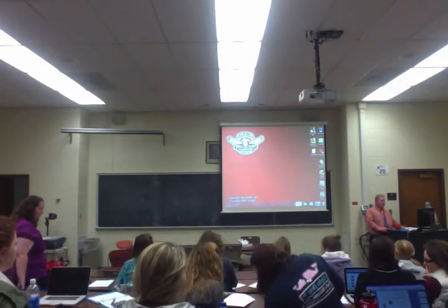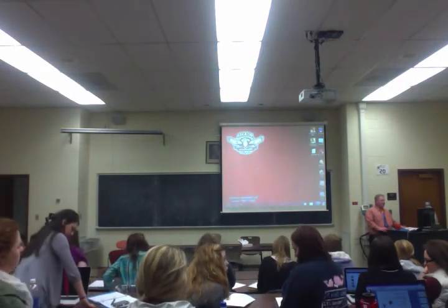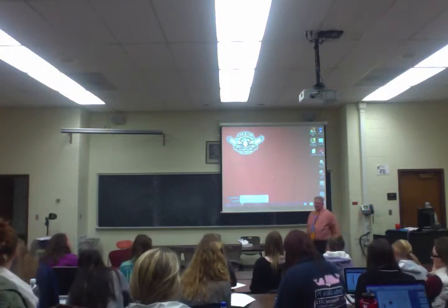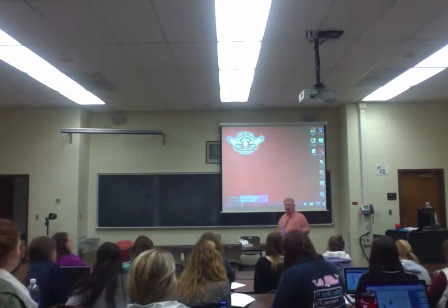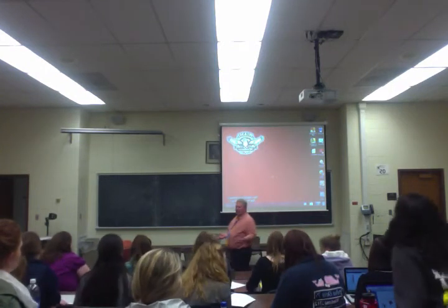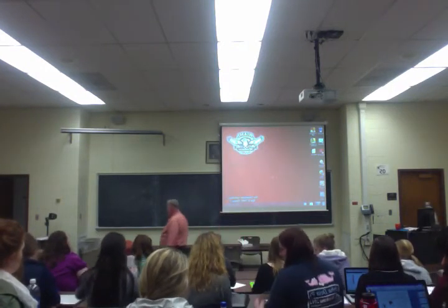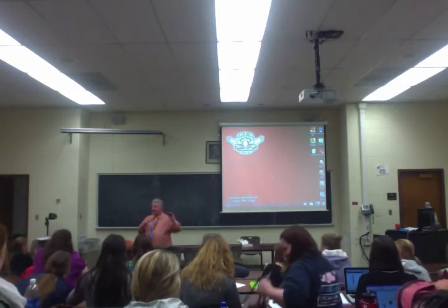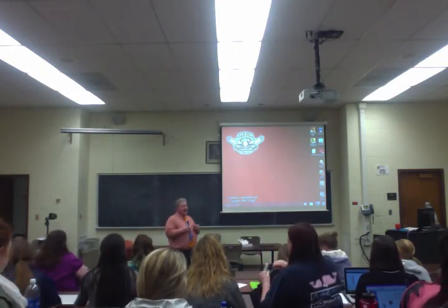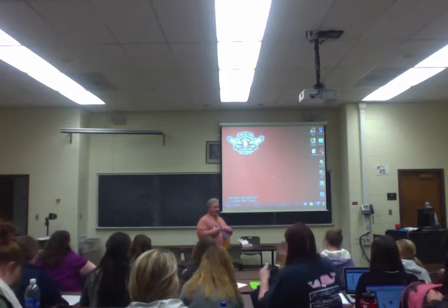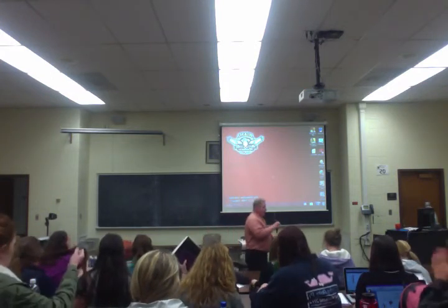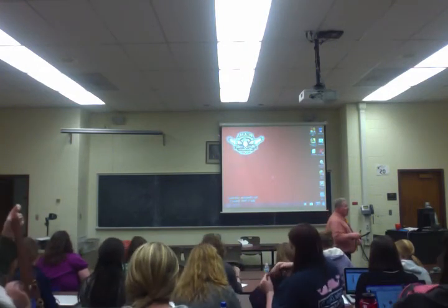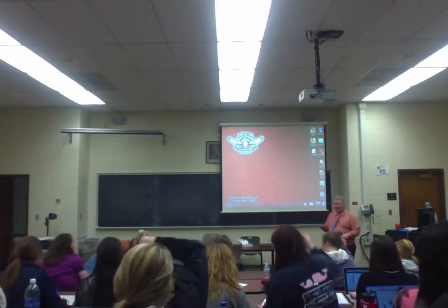That's important because when you're troubleshooting a hearing aid, you need to know where the different parts are so that you can figure out what's wrong. Like I said, you guys are going to be the front line people that they're going to bring the hearing aids to when they're not working. You have to know what's where, so you know where to look, but know that probably 8 times out of 10, there's going to be a blockage somewhere, and you just have to figure it out.